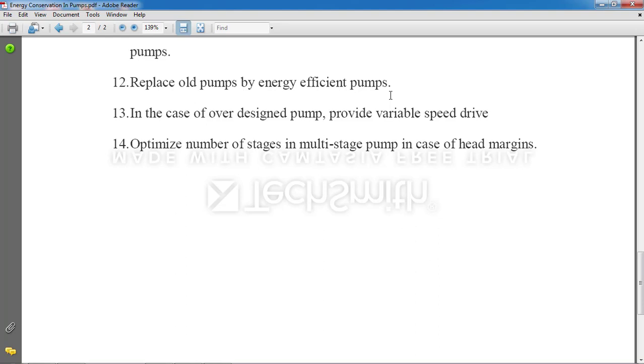Next, in the case of over-designed pumps, provide a variable speed drive. We had already discussed the importance of a variable speed drive. We can control the flow rate according to our convenience, and that's why the variable speed drive, or VSD, is important in a pump.